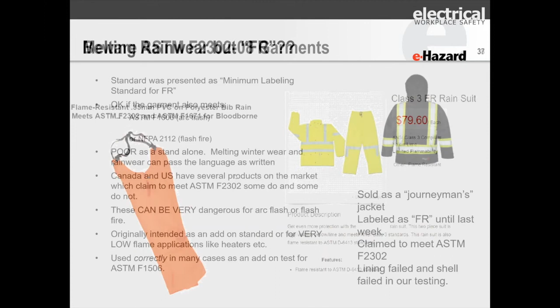Arc-rated materials, your winter wear needs to be arc-rated. OSHA requires it to be FR. FR to OSHA is non-melting FR. It really means it's arc-rated, but the winter wear doesn't have to be matched to the hazard. As long as it's a non-melting 1506 compliant garment, it can be your only protection if you wish, but it doesn't have to be matched to the hazard as long as your undergarments are, and it's non-melting.